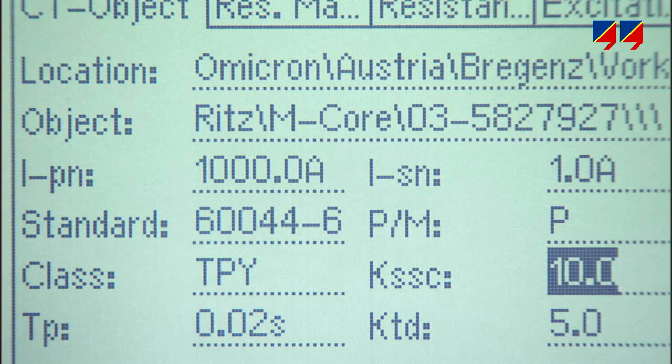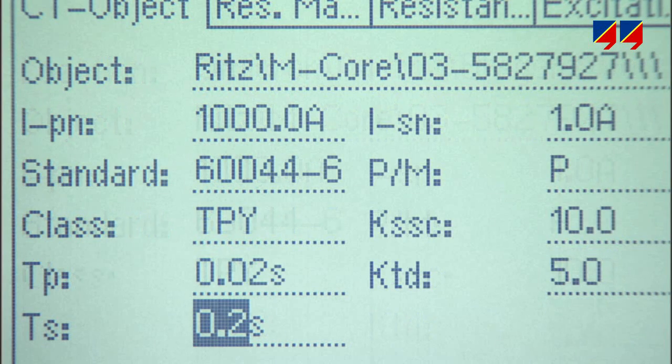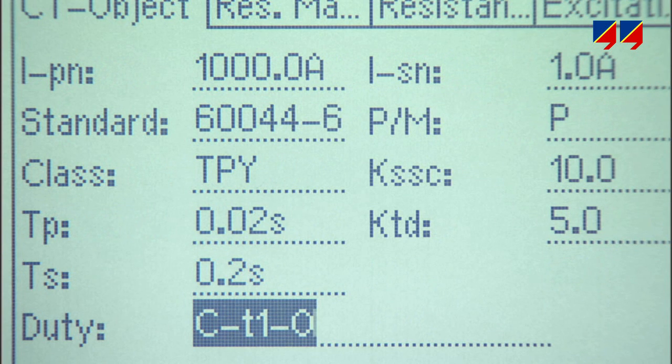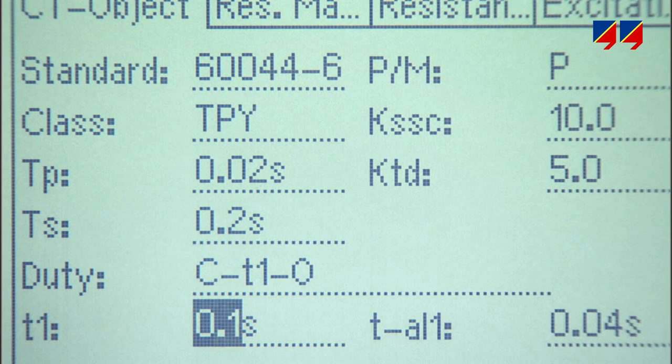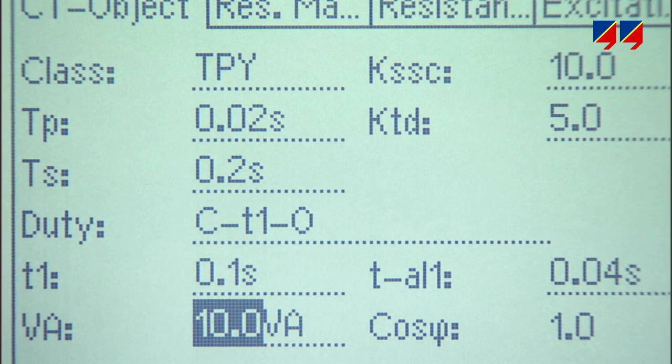When testing such a CT, specification data such as the rated symmetrical short circuit current behavior and the permissible time to accuracy limit can be entered into CT analyzer, which will determine its equivalent model and verify the parameters specified, as with any other CT.